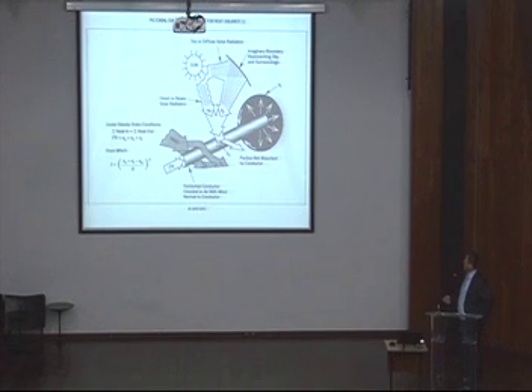I think most of you have seen this. It's an IEEE paper from 1970, so 46 years ago. It's also a very famous demonstration. What impacts the conductor temperature? Easy to say, all heat which goes into the conductor, like the solar or the heat from the I squared R, must go out or must be stored in the conductor. So there's a heat balance equation, and if you know all other input and output parameters, you can calculate the current which gives you the actual temperature, or the other way around. So there's an equation, and the only thing you have to know is all the input parameters.